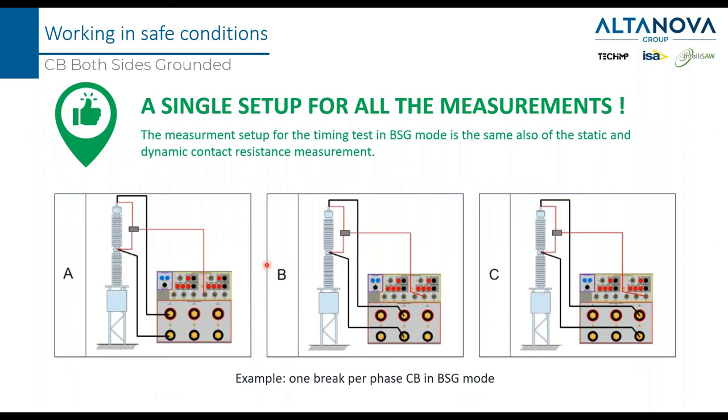The advantage of keeping both sides grounded is that with the same setup used for resistance measurement, you are also measuring the time — a big advantage. With a traditional circuit breaker analyzer, you would perform the connection for time measurement, then disconnect and reconnect for the micro-ohmmeter measurement. With a device able to measure time in both-sides-grounded mode, you only need to perform the wiring once and do all your tests.